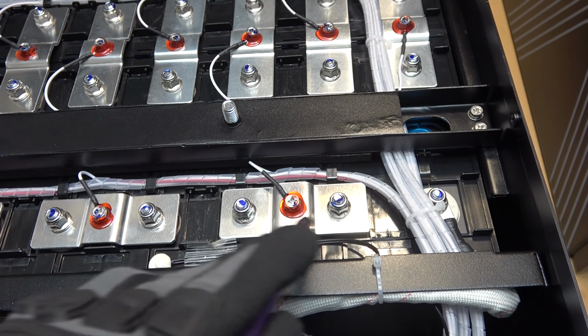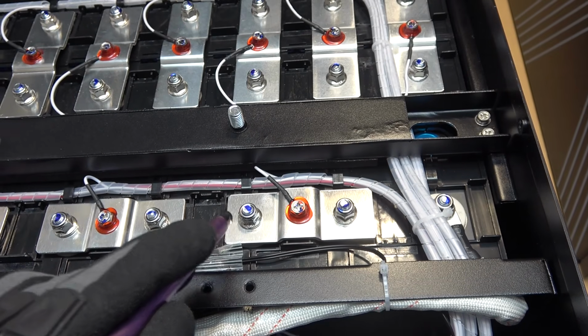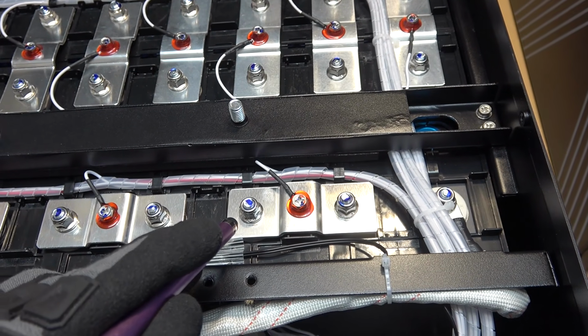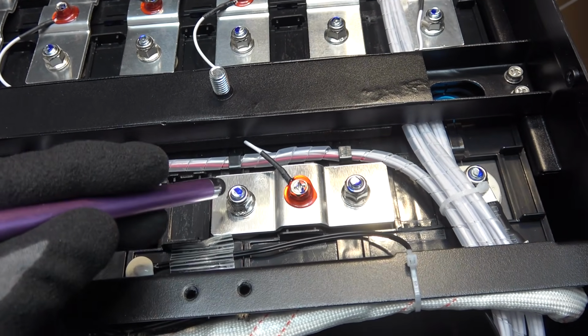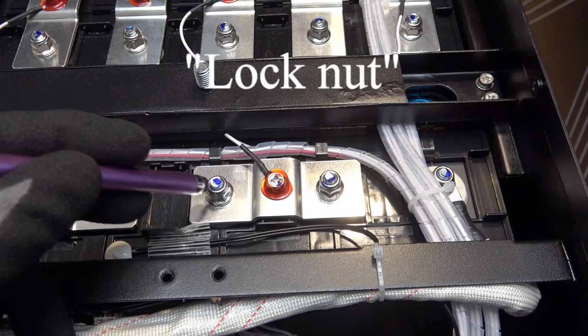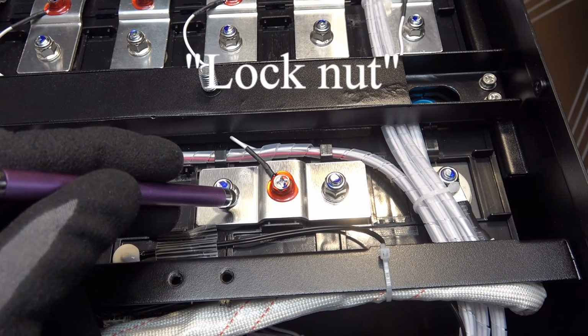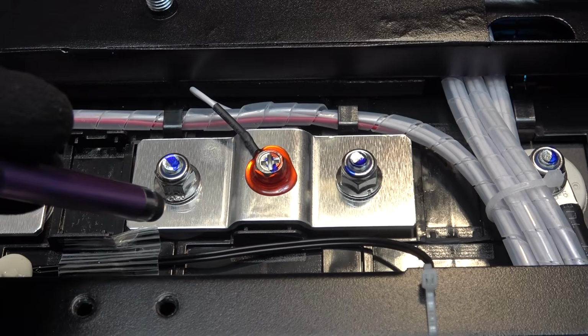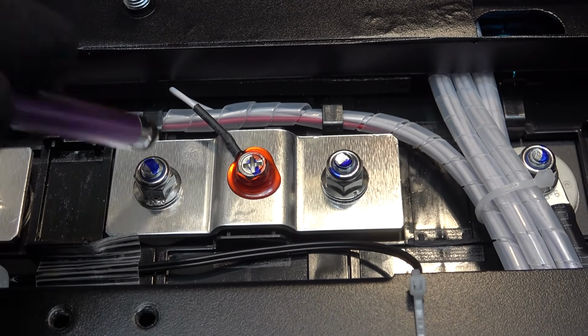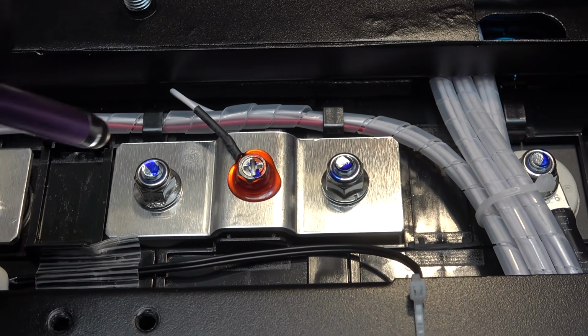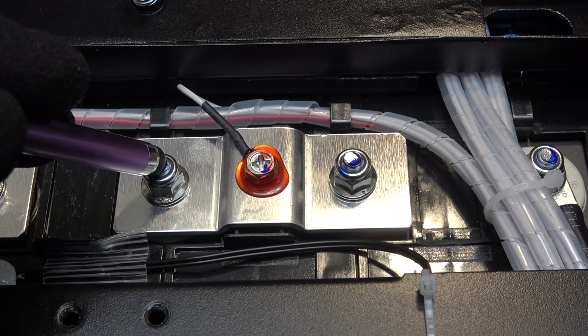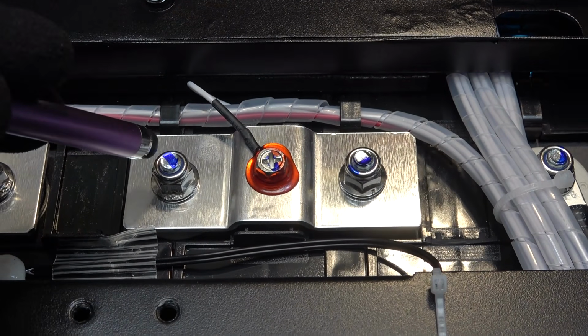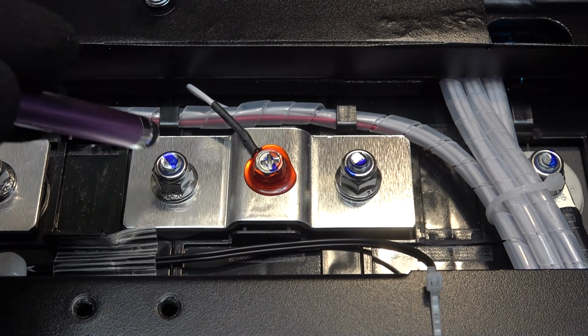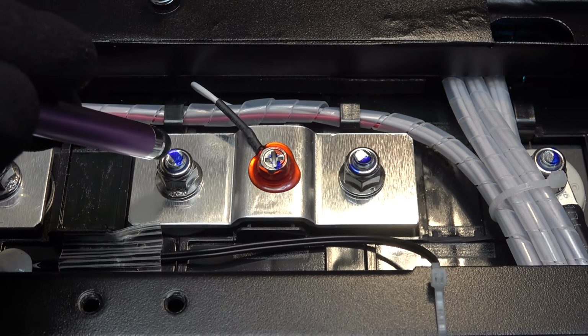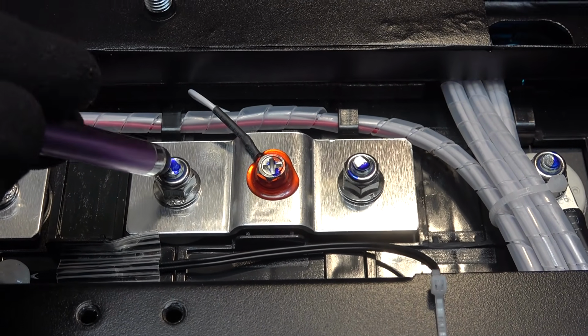The series connection is made by an aluminum bus bar, and it's not welded onto the cell, but rather they use a lock nut, and that's to ensure it doesn't get loose. Most other batteries will weld the aluminum bus bar onto the battery terminal, but this one uses a lock nut, and I like this better because if one cell goes bad, you can actually remove the cell and put in a new cell very easily.